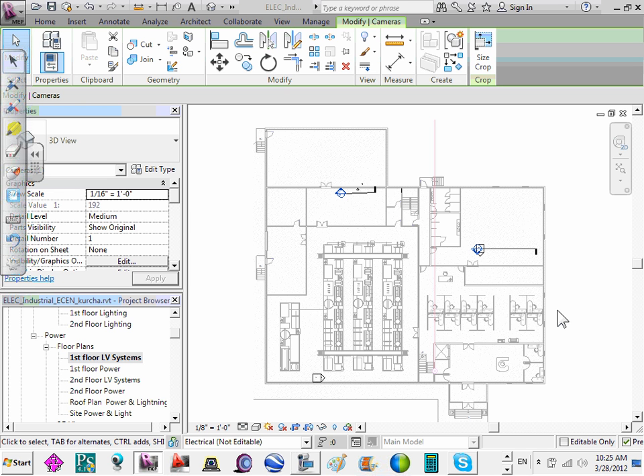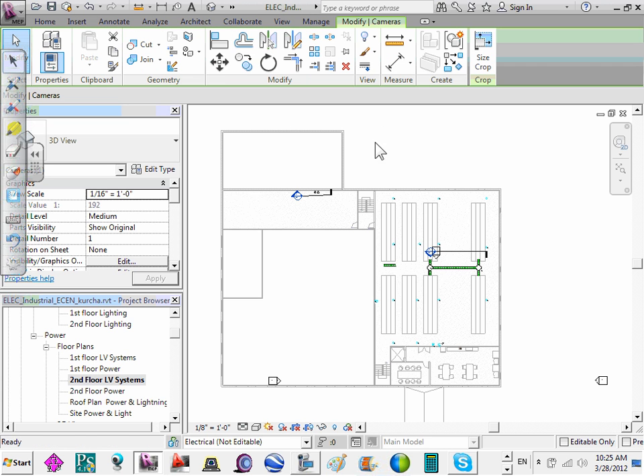Let's jump into it. All right, B occupancy fully sprinkled according to the Minnesota State Fire Code, the 2007 version, which is what we're currently on. For B occupancy fully sprinkled, no fire alarm system is required, except for monitoring of the sprinklers, flows and tampers. You're going to have duct smoke detectors in the return side of the air handling units, or anything above 2,000 CFM. That will be here.